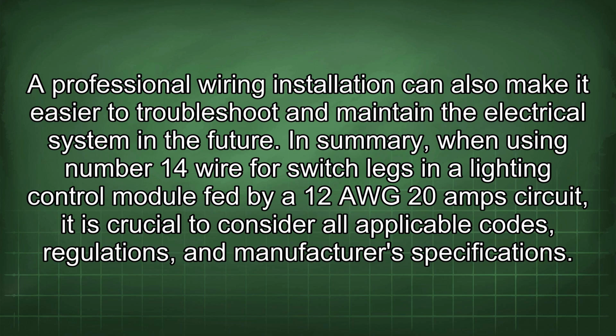In summary, when using number 14 wire for switch legs in a lighting control module fed by a 12 AWG 20 amp circuit, it is crucial to consider all applicable codes, regulations, and manufacturer's specifications.